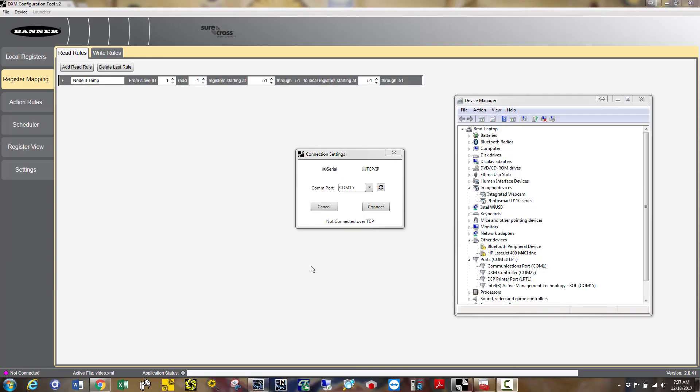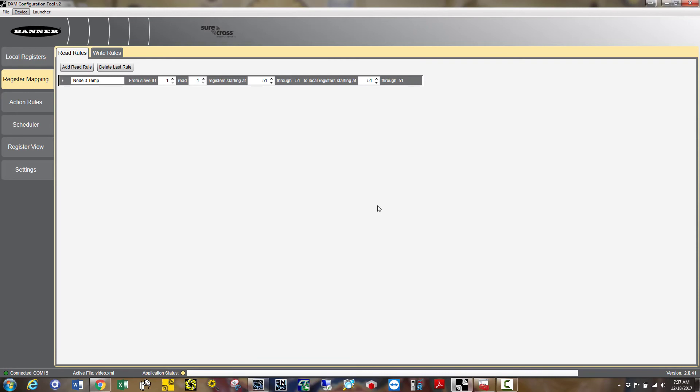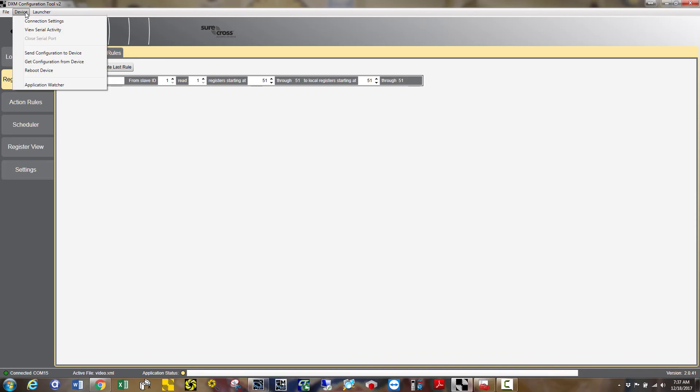To send this to your DXM, first save your configuration. This example will utilize the USB connection. Under connection settings, make sure your COM port matches your computer's COM port settings and choose connect. Connected should light green. Then choose send configuration to device.